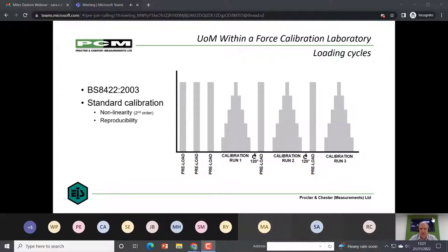You then run the first calibration cycle with a minimum of 5 equidistant, equispaced points. You take up to each point, hold it for 30 seconds, and then take the measurement before proceeding to the next. You then drop down in exactly the same measure, coming back down to zero. At this point, you will take the device out, rotate it through 120 degrees, and then conduct a single preload or proof load up to full rated load, hold for 60 seconds, and then you run your second calibration cycle, and then you take the device out, rotate through 120 degrees, and then again you do the preload and the full calibration run again.